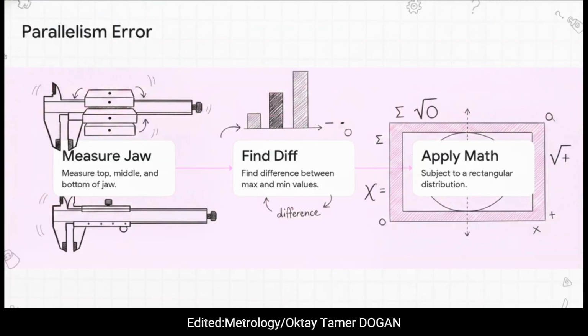First, the tech takes measurements at 3 distinct points on the jaw: top, middle, and bottom. Second, we extract the maximum and minimum values from those tests and find the exact numerical difference between them. Third, and this is the vital statistical part, that difference gets plugged into a mathematical model called a rectangular distribution. It sounds fancy, but applying a rectangular distribution essentially just assumes the true error has an equal probability of falling anywhere within those max and min limits. By doing that, the uncertainty from jaw parallelism is accurately captured and legally added to the final certificate.